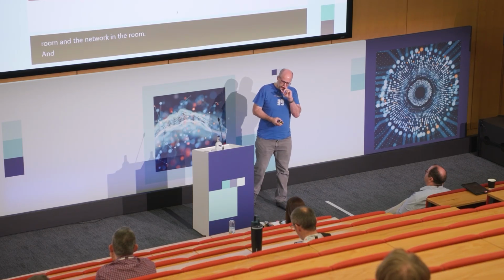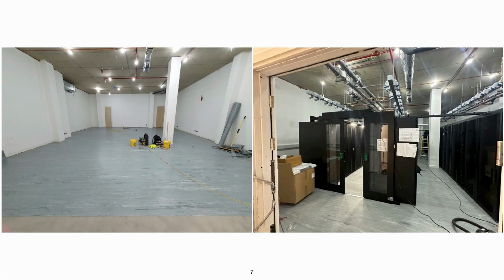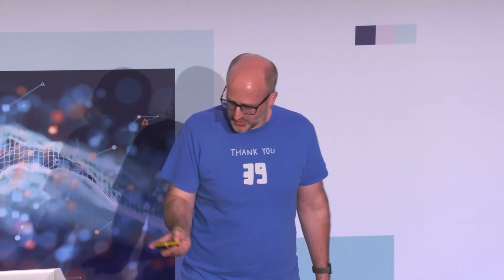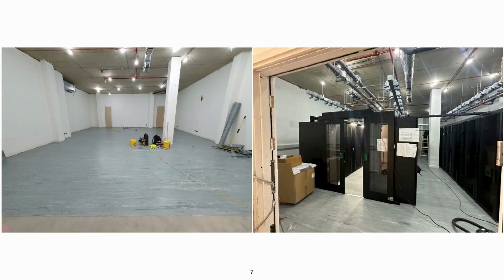And then just a couple of pictures. On the left, you see the room as it was emptied. Essentially, for this project, we had to turn off the data center for 3 months. So we couldn't run for 3 months. But for us, that's not a problem because we're doing the LHC. There are 5 other sites in the UK, 100 others across the world who can pick up the slack for those 3 months. So we were not missed for 3 months, but we would have been missed for longer than 3 months. So the room as it was emptied, and then about 6 weeks later, you see what happened on the right. We've already got our cabinets, our containment for the hot aisle, and you can see above the racks the power and the cooling.